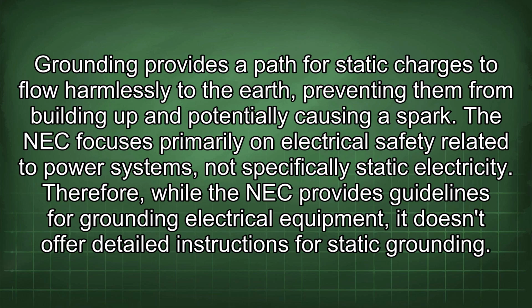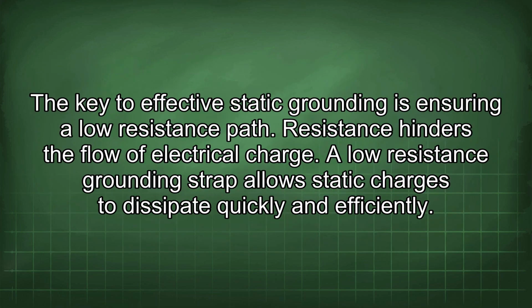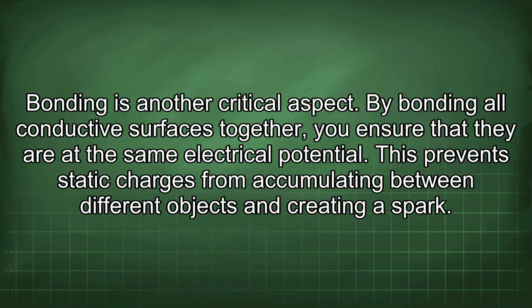Therefore, while the NEC provides guidelines for grounding electrical equipment, it doesn't offer detailed instructions for static grounding. The key to effective static grounding is ensuring a low resistance path. Resistance hinders the flow of electrical charge. A low resistance grounding strap allows static charges to dissipate quickly and efficiently. Bonding is another critical aspect. By bonding all conductive surfaces together, you ensure that they are at the same electrical potential. This prevents static charges from accumulating between different objects and creating a spark.